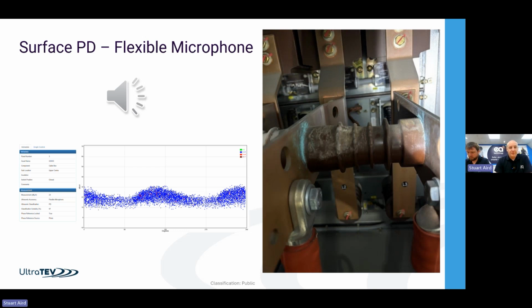This particular survey had been done just before an outage, so we made the recording, we spoke to the customer, and we advised them that there's a possible problem in this panel, so they could open it up and have a look. We could see the clear tracking across the surface of that area. I don't think it would have lasted too much longer. A lot of these things are affected by humidity as well, so try and control the humidity in your substations.